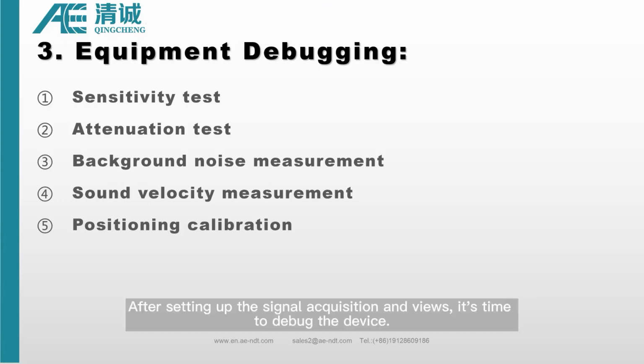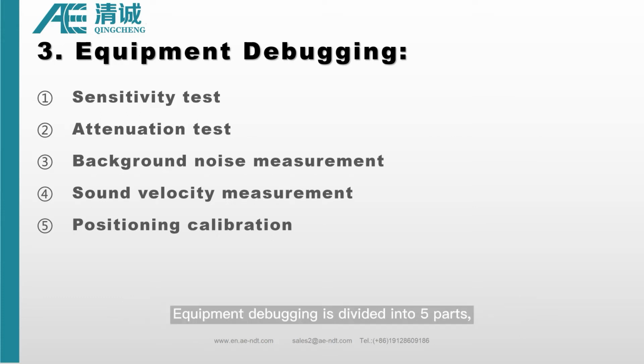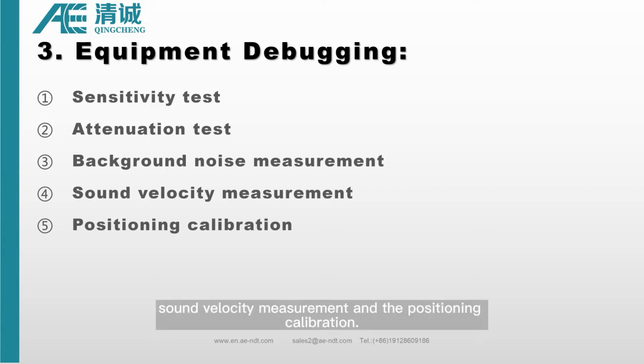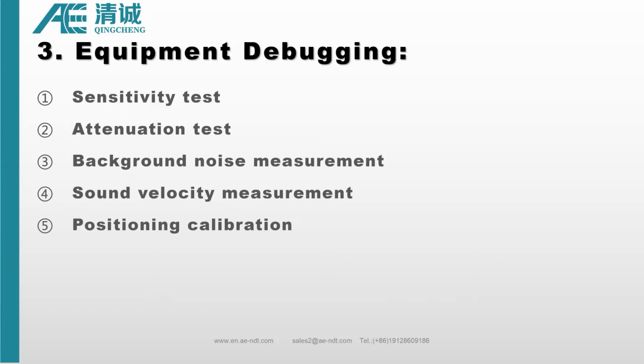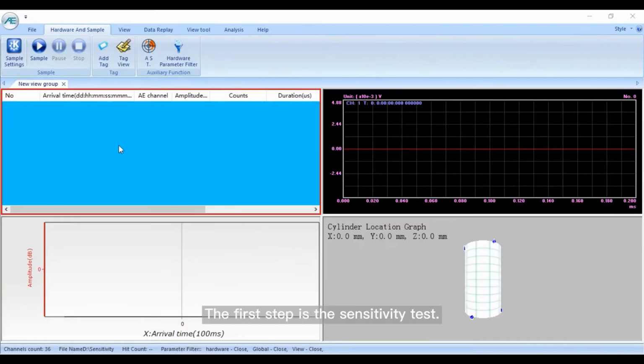After setting up the signal acquisition and views, it's time to debug the device. Equipment debugging is divided into 5 parts, including the sensitivity test, attenuation test, background noise measurement, sound velocity measurement, and the positioning calibration. The first step is the sensitivity test.